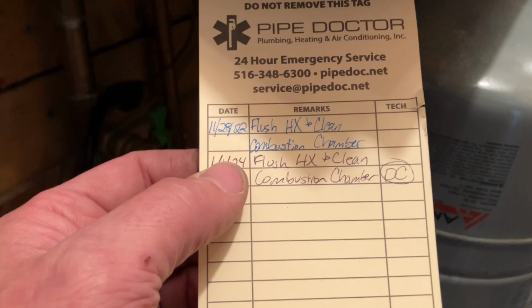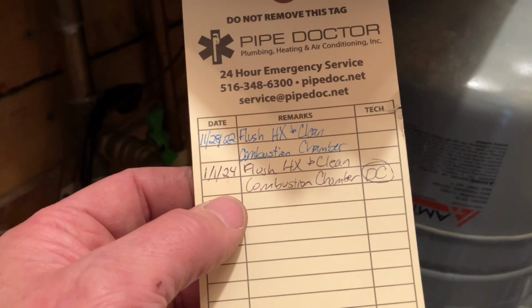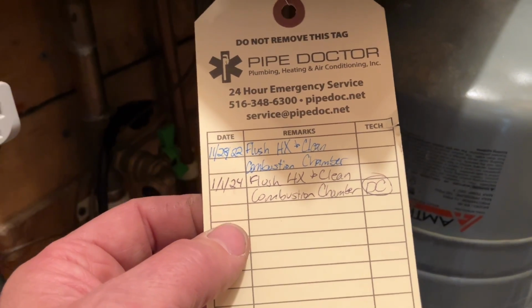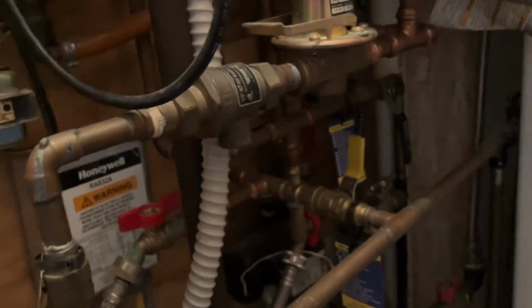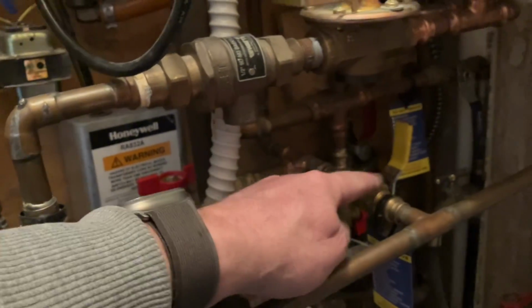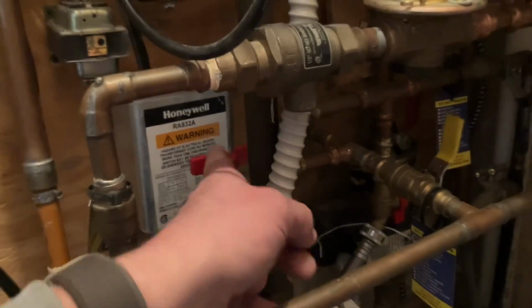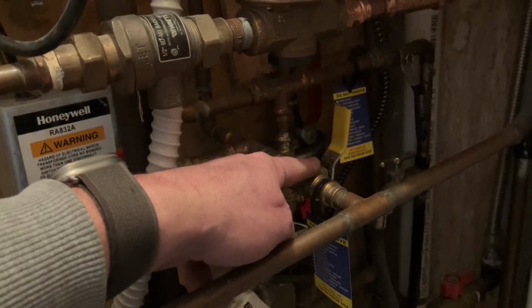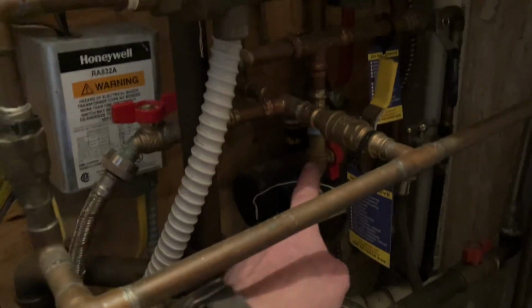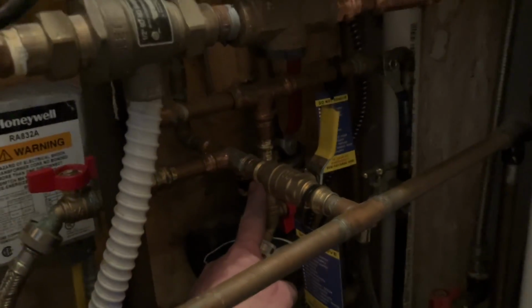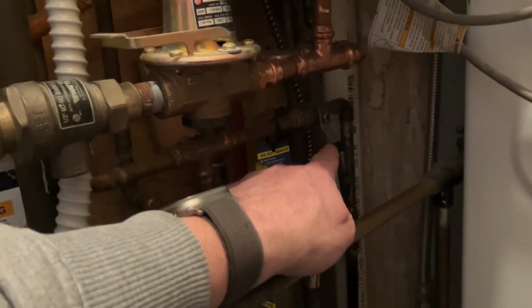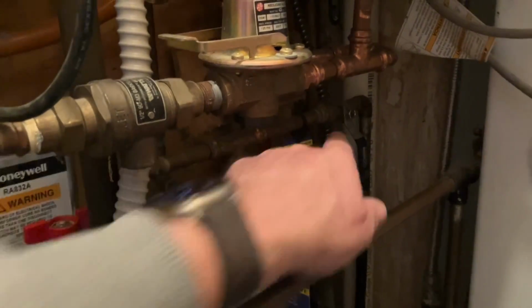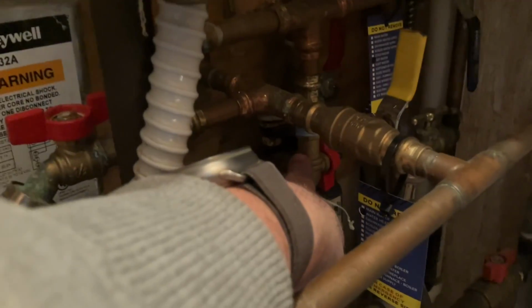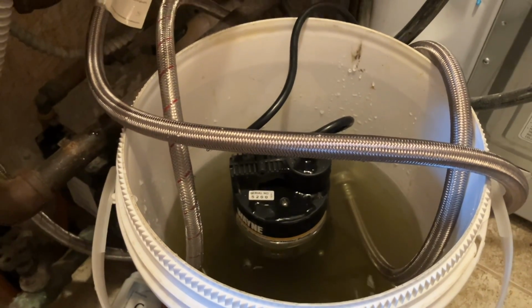Alright, we got this Baxi Luna. We've been coming here for a couple of years already to clean the combustion chamber and flush out the heat exchanger. For many years, this valve on the domestic cold water side, this boiler drain, after this 1/2-inch ball valve, and this ball valve before the domestic hot water outlet and ball valve. This boiler drain didn't exist, so you can never flush out or decalcify the heat exchanger.